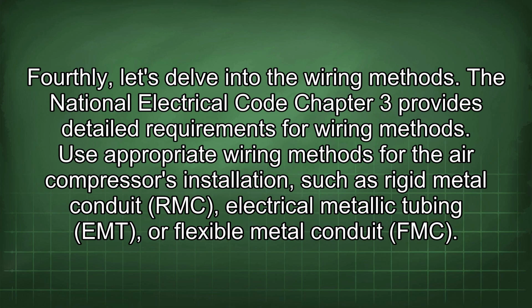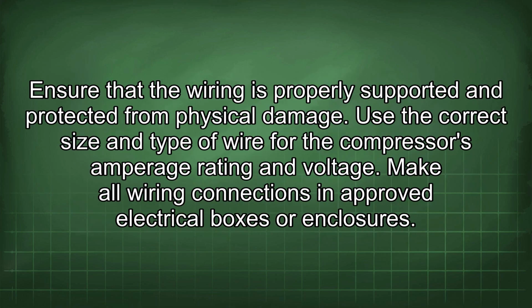Fourthly, let's delve into the wiring methods. The National Electrical Code Chapter 3 provides detailed requirements for wiring methods. Use appropriate wiring methods for the air compressor's installation, such as rigid metal conduit (RMC), electrical metallic tubing (EMT), or flexible metal conduit (FMC). Ensure that the wiring is properly supported and protected from physical damage. Use the correct size and type of wire for the compressor's amperage rating and voltage. Make all wiring connections in approved electrical boxes or enclosures.